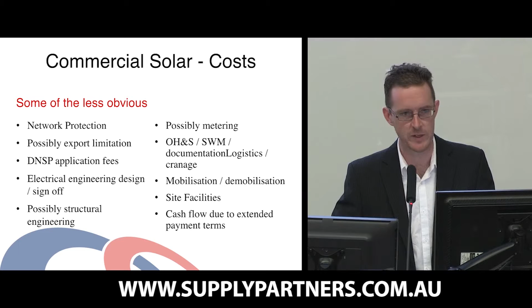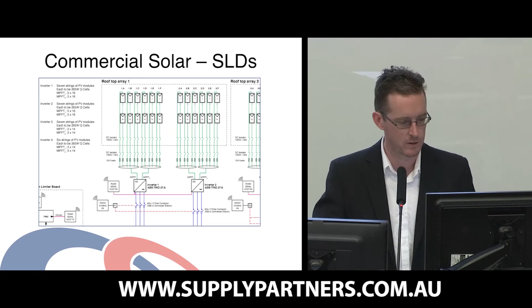One of the things we do to help people tackle commercial projects, perhaps for the first time if you've been primarily in the residential sector, is we can produce SLDs for your project. Just to zoom in, here in the bottom left of the diagram, you can see we've got CTs connected to one of our boards, along with an E-gauge monitoring system. E-gauge is actually the unit that was showing us these graphs earlier for that Gold Coast install. And then up with the inverters, you can see we're actually using radio networking equipment here. This is an example where the feed-in limiter board is adjacent to the MSB, but the inverter locations are somewhere else. At times, you can run physical hardwired cable, and that's great if that works. At other times, that can be very difficult or impossible, and it is possible to use radio networking equipment, which we can provide.